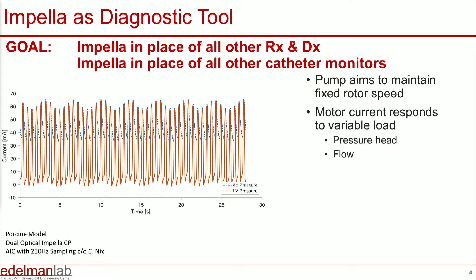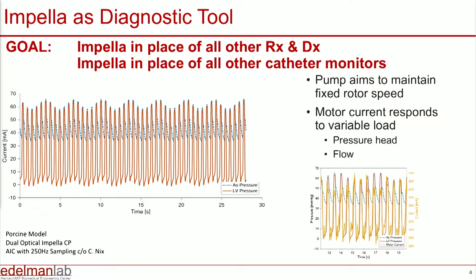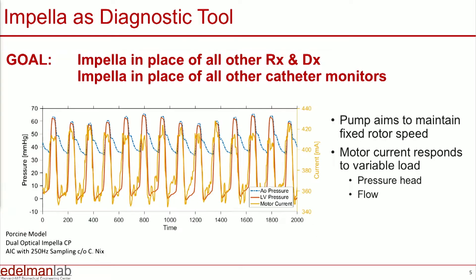This is the aortic and left ventricular pressures sweeping across over a very large number of cardiac cycles. What's interesting is that the Impella, beat to beat, maintains its rotor speed as constant by changing the amount of current fed to the rotor. In addition to the sweep of aortic and left ventricular pressures, you see in yellow the motor current being fed to the rotor. When highlighted at a faster sweep speed, you see the aortic pressure, left ventricular pressure, and some natural respiratory variation, but the motor current undergoes subtle variation.